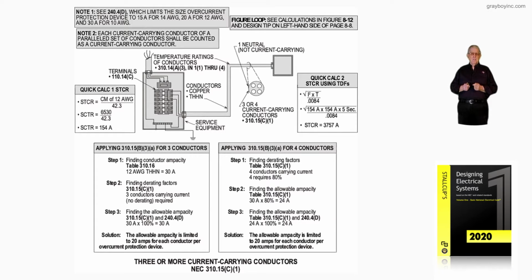Now this illustration deals with derating for ambient temperature, which are called correction factors. Remember, where we had more than 3 current carrying conductors, those were considered adjustment factors. Now, notice that tables 310.15B1 or B2 as in boy are used here. But notice we only have 3 current carrying conductors in our raceway.